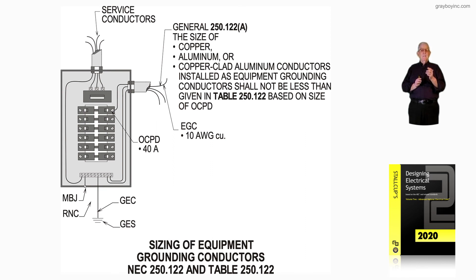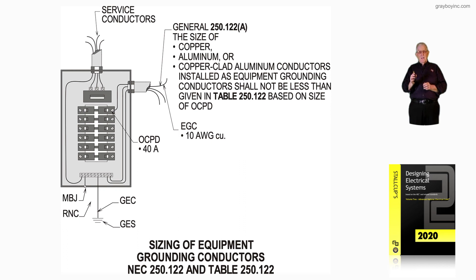The grounding conductor — the main bonding jumper — would be sized per Table 250.102C1. That's a good illustration of supply-side grounding and load-side grounding, and that's what figure 16-113A is illustrating.